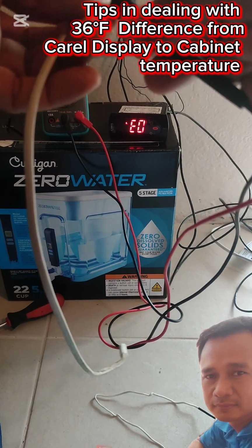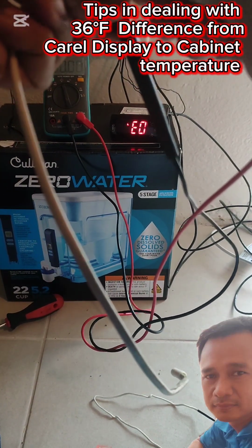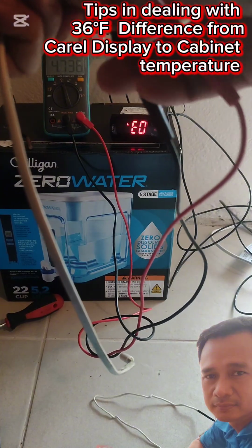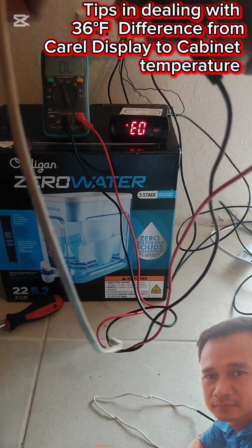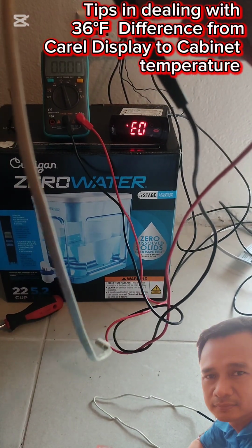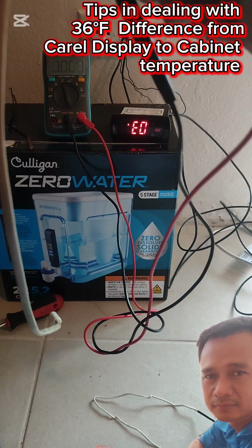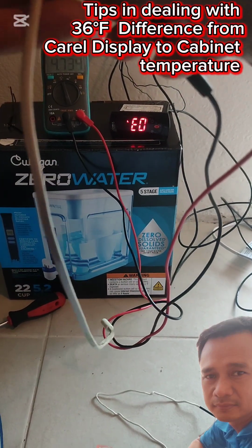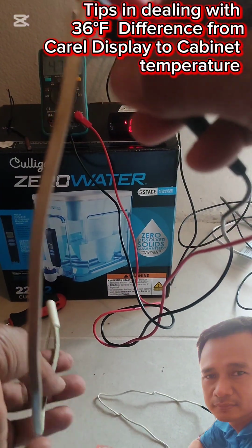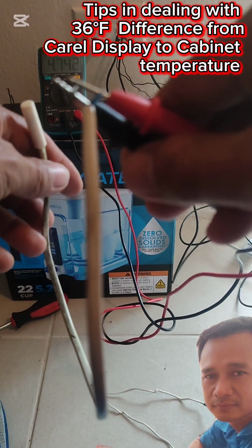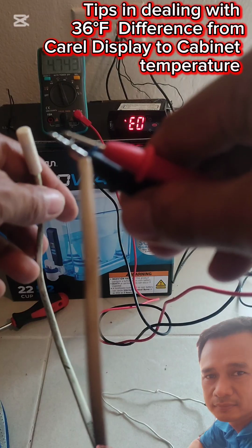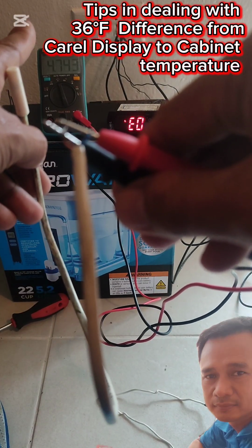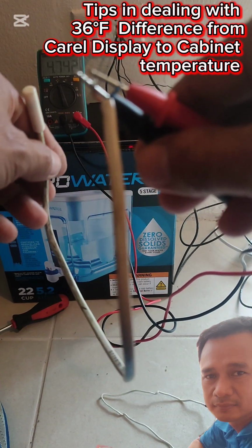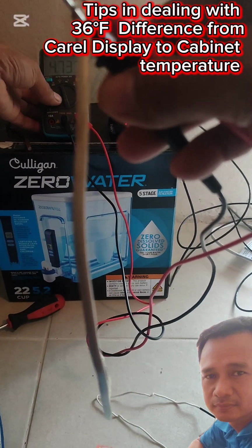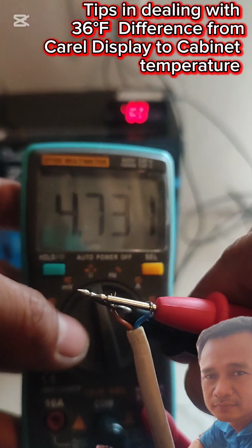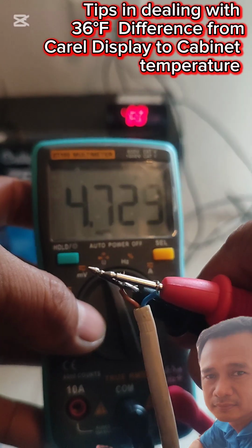I just press the set button to silence it, otherwise some will get annoyed and start messaging me about the annoying sound. There it is. Here's the sensor I just took out, and look at the reading. It's 4.7 kilo ohms. I'm going to get this so you will see it. It's 4.7 kilo ohms.